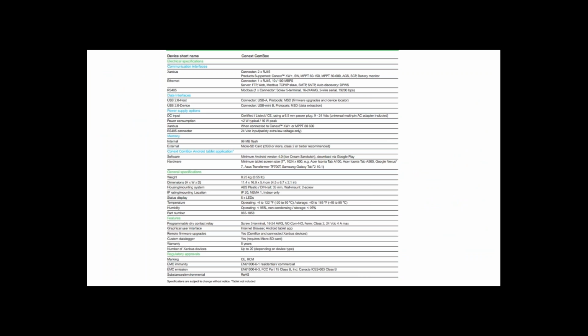Here are the specs for the Conext ComBox. In particular, we might want to talk about the low power consumption, less than 2 watts is typical. RS-485 connector is available for RS-485 Modbus Communications. It has a micro SD card port for custom data logging, 96 megabytes of flash memory. We do have Android version, Ice Cream Sandwich 4.0 for the Android app. The size and weight are listed. NEMA, indoor only. These are not outdoor rated devices. Status display, part number, remote firmware upgrades, yes. Custom data logger, yes. 5-year warranty.